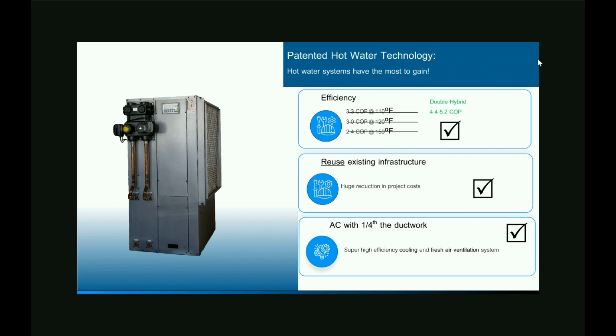you have to put that air in close proximity to where it's going to be used. You have to put your heat pumps in relative proximity to the spaces that you're trying to heat up, right? You want to spread them all throughout a building. But if you do that, you can check all three major boxes. Efficiency increases dramatically because of the energy recovery. We typically see, it depends on, of course, what temperature you're running at, but a COP of 4.5 to 5 is 100% achievable. We can reuse all of the existing infrastructure.